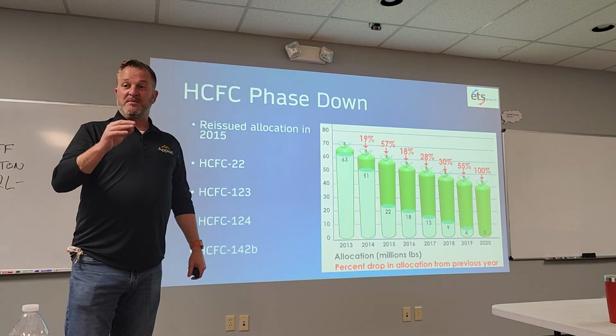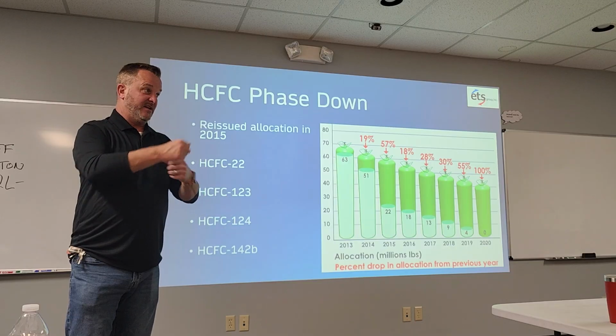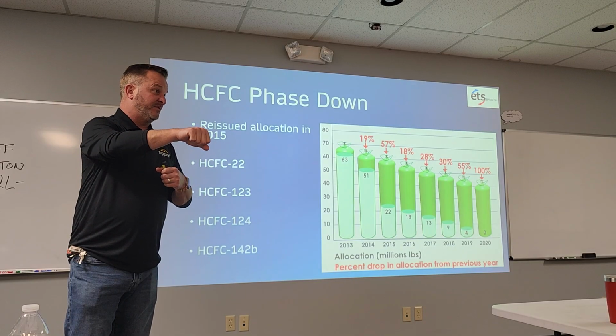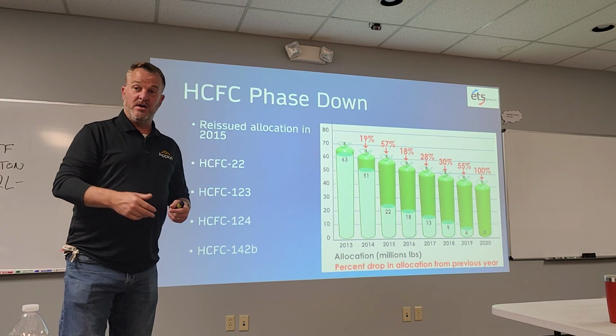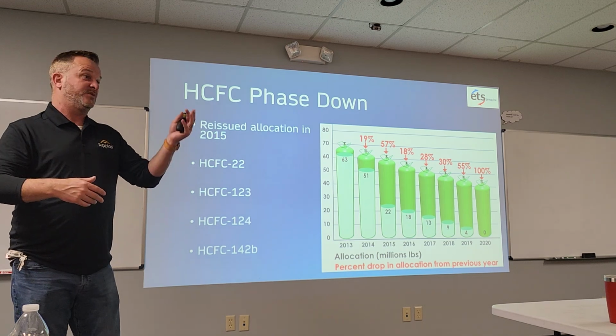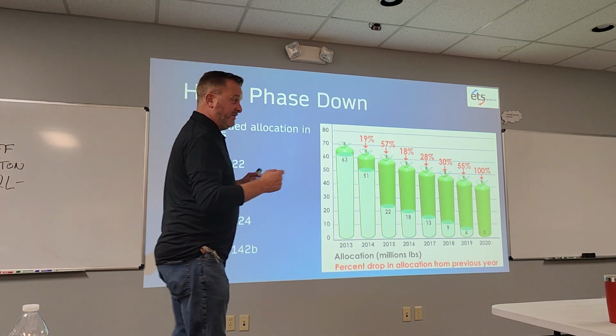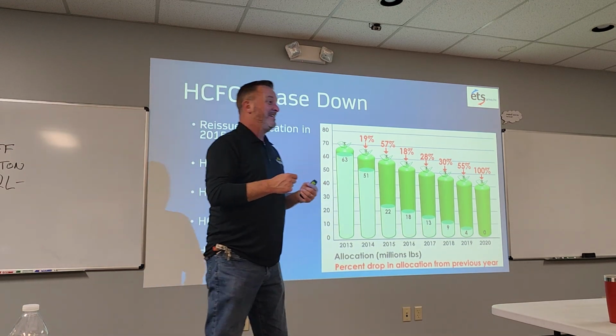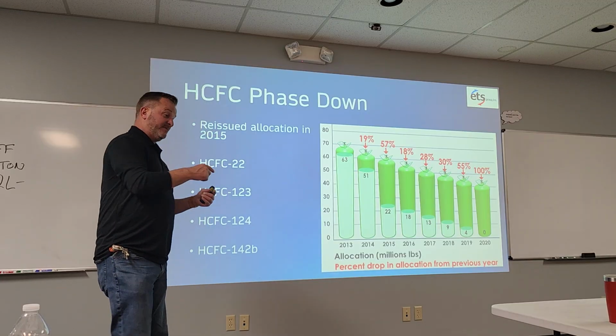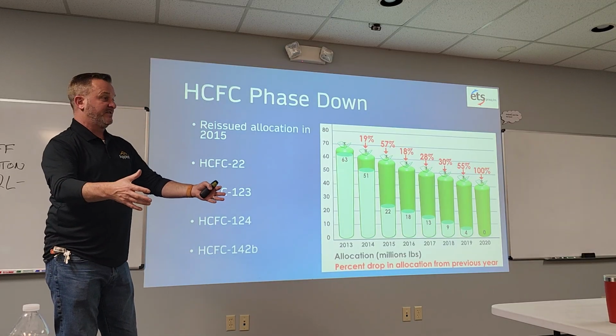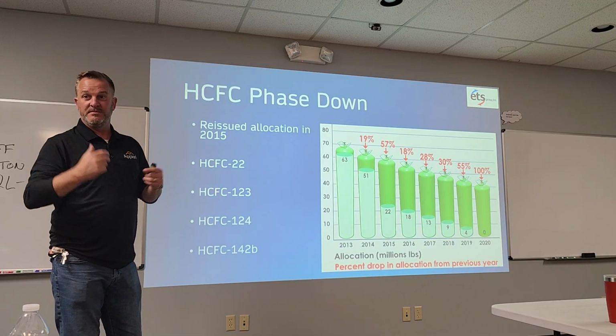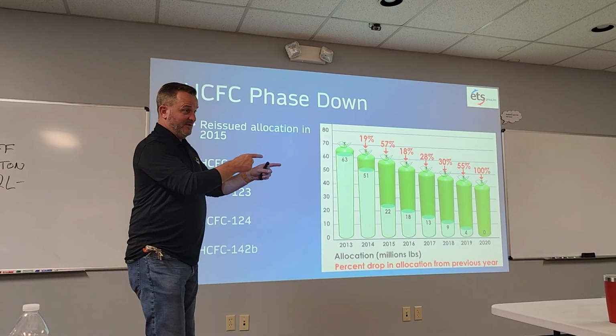That's one of the main reasons - you might remember when you take a full recovered cylinder into the distributor, they'll say, okay, we'll give you so much per pound of R22 or whatever else. You always pretty much got disappointed, because say you turn in a recovered cylinder of R22 thinking, man, this is gold, I'm going to get some good money for this - they would send it in to the reclaimer.